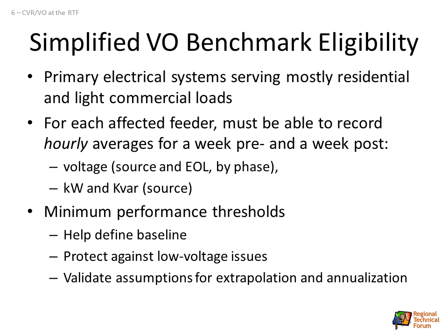So if you have a total voltage drop between source and end of line of, say, 5 volts, then halfway down that feeder you've got about half that voltage drop. That's important for extrapolating the delta V that's being seen by the customers. And if you have a system that's kind of all over the map, those calculations just don't work—or at least the simplified versions of them don't, that are baked into the protocol.